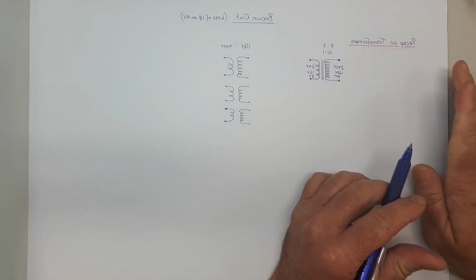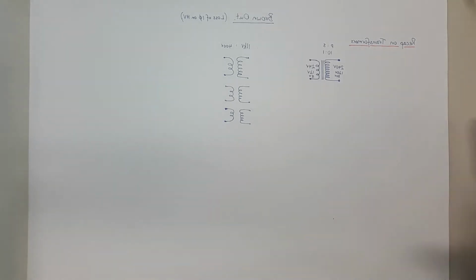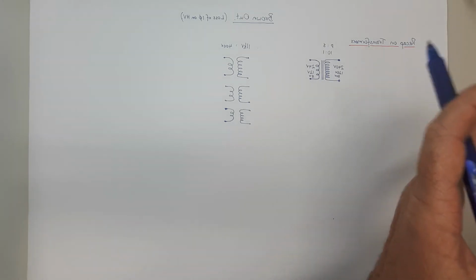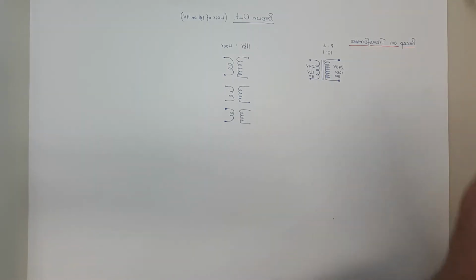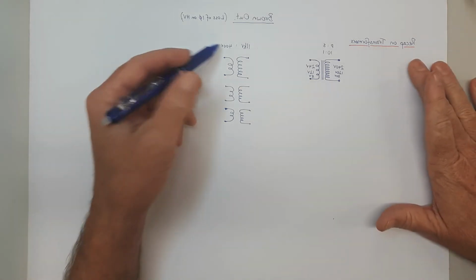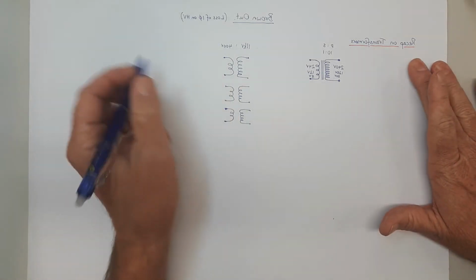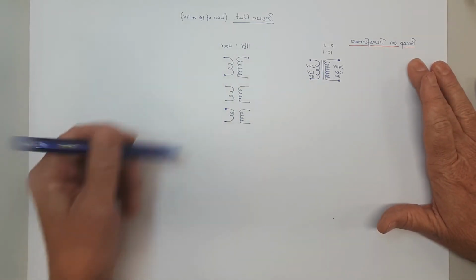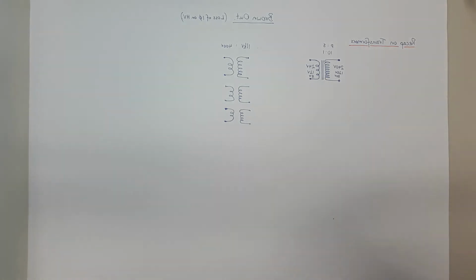Now, the trick with the transformers that you see, you can see hundreds of them out on the street, especially the ones that are mounted on poles. They're a lot easier to have a look at. And so you can see the 11 kV mains coming in. There's three 11 kV wires, and of course we know that our low voltage is 400. You've got the 3 phases and neutral. So that's the basics of that.